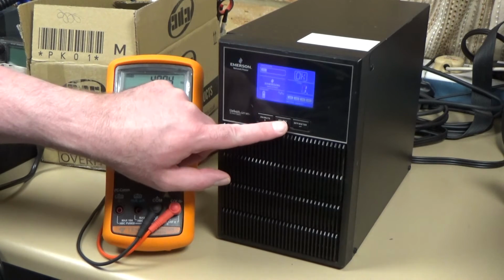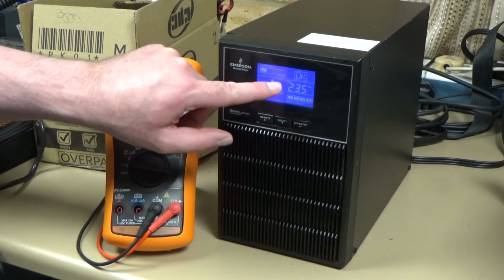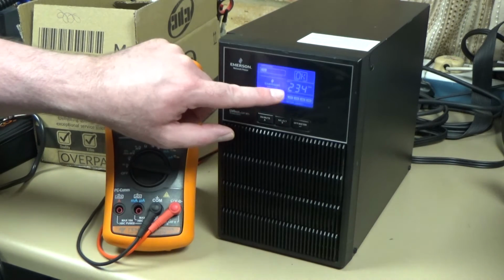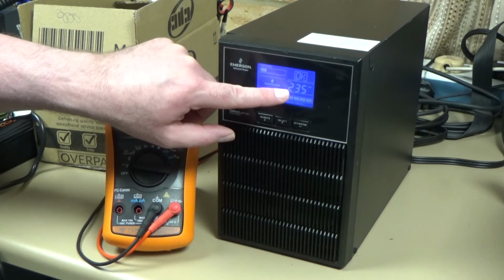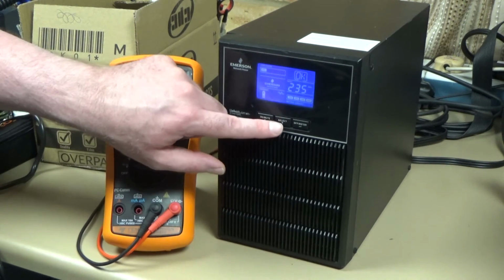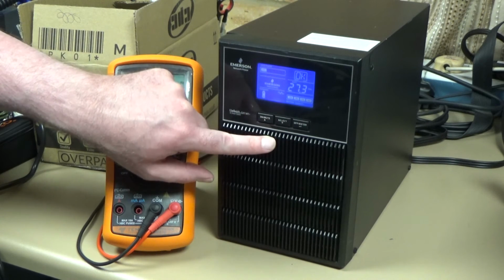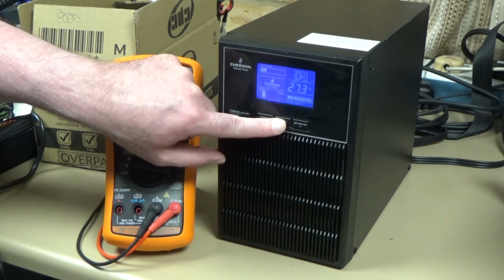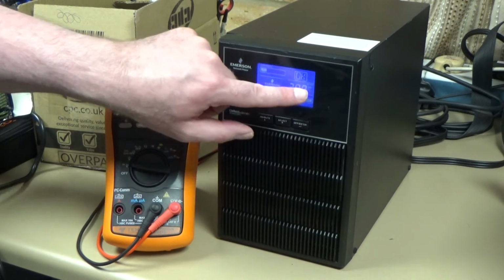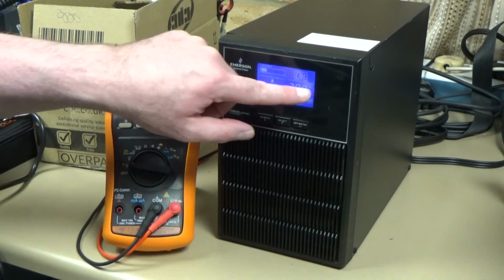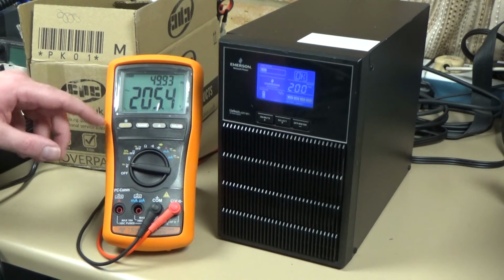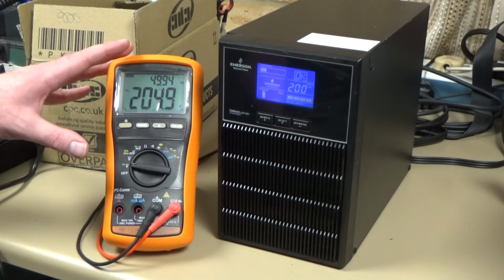This has changed because I pressed the select button. That's now the input voltage, which is 235. That's actually quite low for this location, it's normally about 242, 243, that kind of range. And that's the battery voltage. That is the output voltage, which is telling me is 200, so I suppose 205, 206 is within tolerance for 200 volt output.